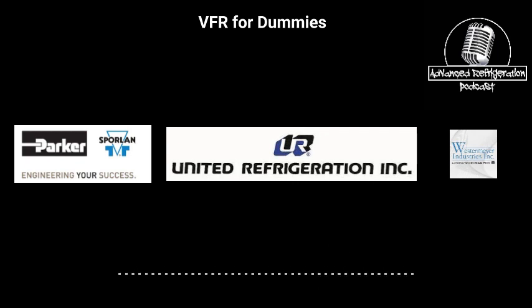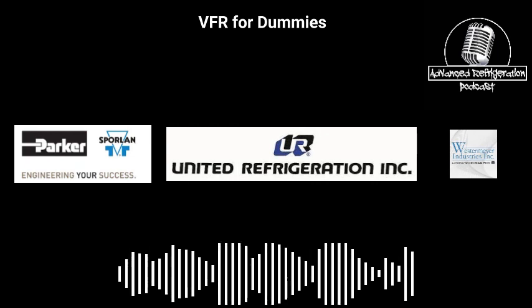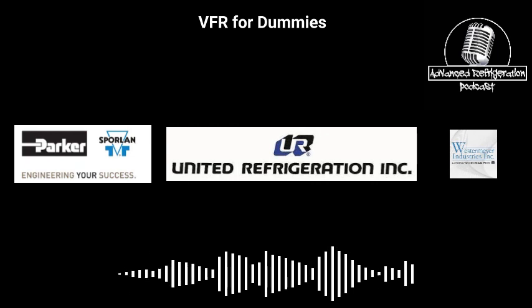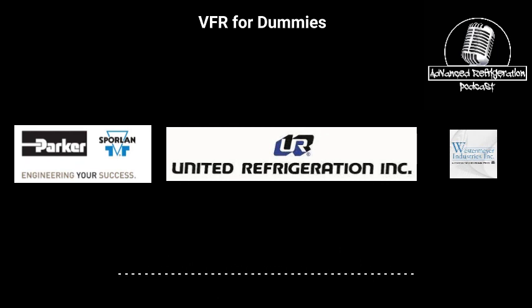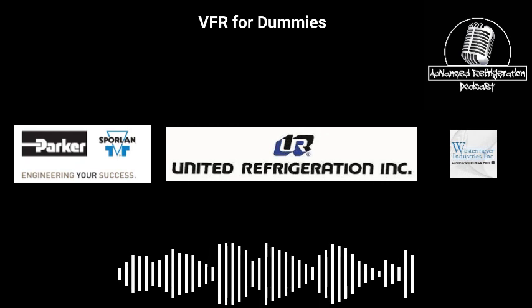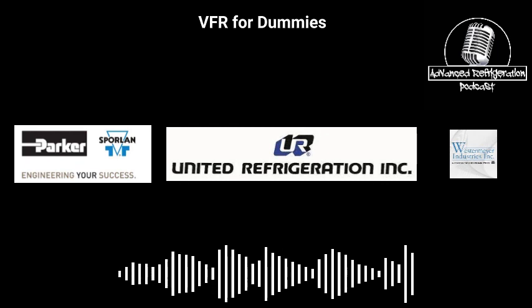Shit. Like the whole branch box? There's no serviceable components in the branch box. It's filled with expanding foam, so there's nothing inside here you can change. You can pop the heads off, but you can't get inside the box. So say you had a branch box with like five or six circuits on there, one valve fails, you got to change the whole branch box?